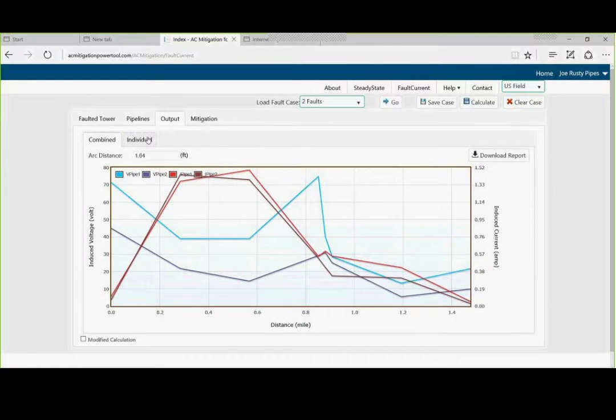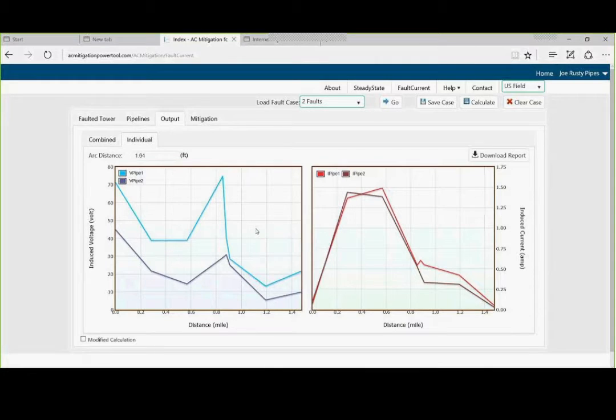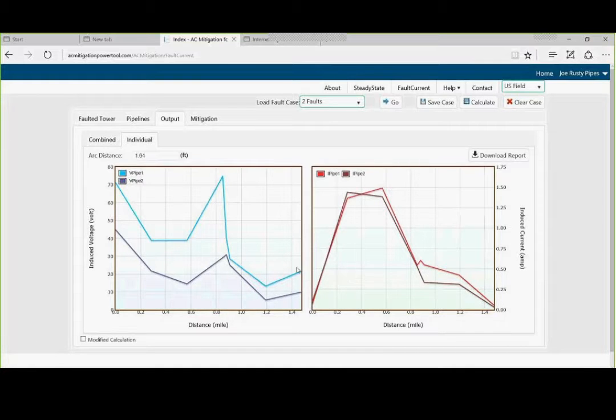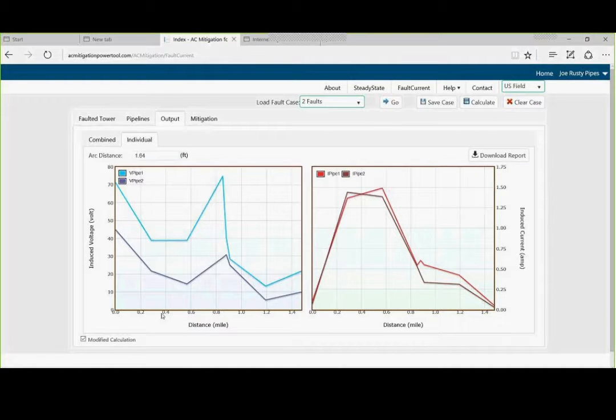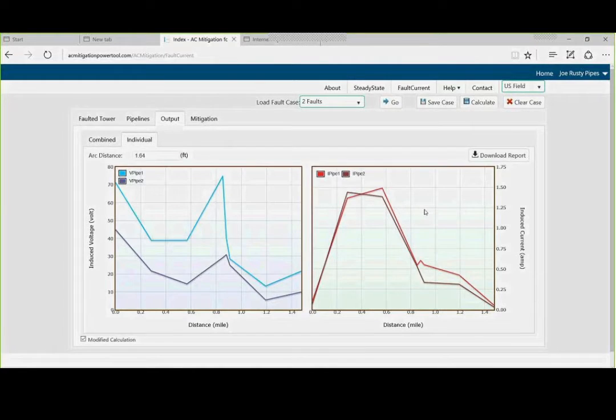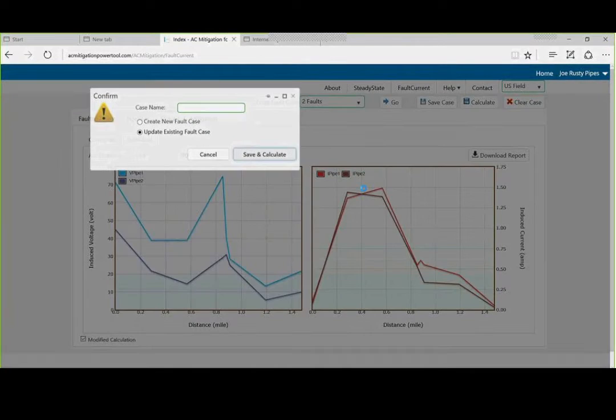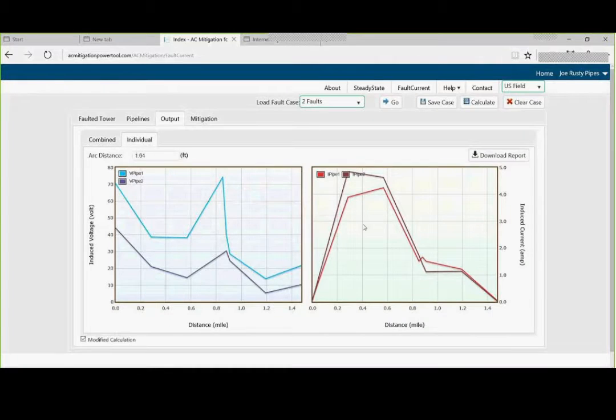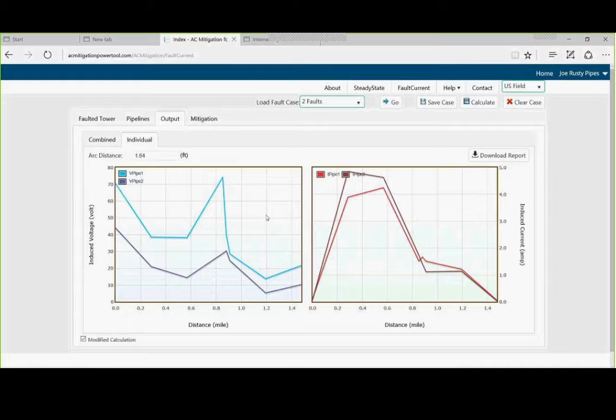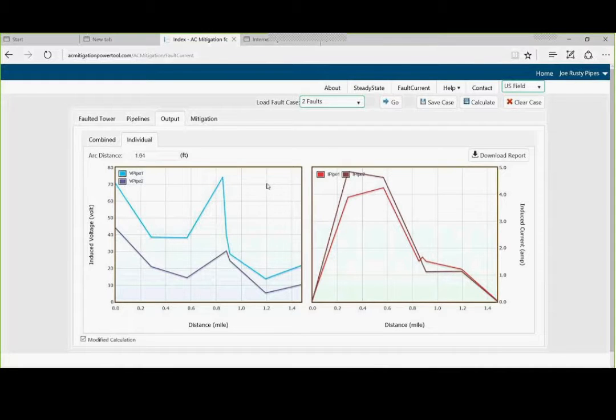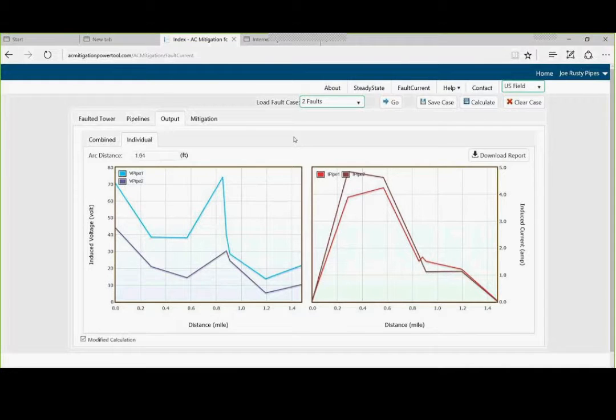It says it's good. I like to look at it as individual. And it says that we have 70 volts on one end and basically 20 volts on the other end. So, we're in pretty good shape. We also have an arc distance of 1.64. And also, we could do a modified calculation if we want. And we could calculate it again. And this is sometimes just to adjust your voltages to tweak them a little bit. There are times that they may be off of volts or so. And doing the modified calculation will bring these into alignment by tweaking it. So, again, this doesn't look bad.